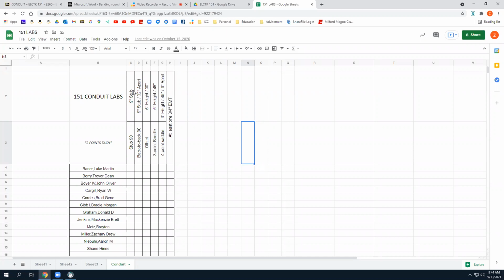Corey? So you couldn't use the arrow for both sides if you wanted to? Could you? Yes. Why wouldn't you want to? It's not that it's not the proper way. It's just you have to do extra math. It's not that hard of a math, but if you know the distance apart, like you're going to have to know the distance apart for either way you bend it. With your method, with the take-up method, then you have to measure back 5 inches, put it on the arrow, and bend it up. So the star helps you skip a step, right? Does that make sense? Yeah. Okay, so that's a back-to-back 90.